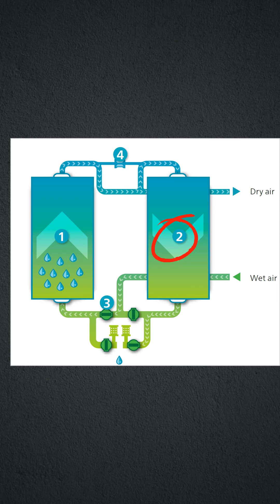Step 2: Regeneration. Dry air from the drying tower outlet is expanded to atmospheric pressure and sent through the saturated desiccant, forcing the adsorbed moisture out. After desorption, the blow-off valve is closed and the vessel is re-pressurized.